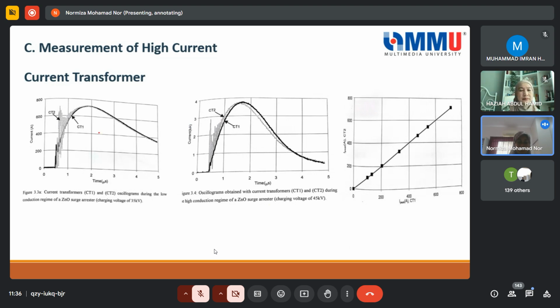So this is just to share the current transformer when we have the calibration. We have two current transformers, and we calibrate. One is producing very high oscillation, whereas the other is more steady and without oscillation. So in our selection, we have used CT1 throughout our measurement.